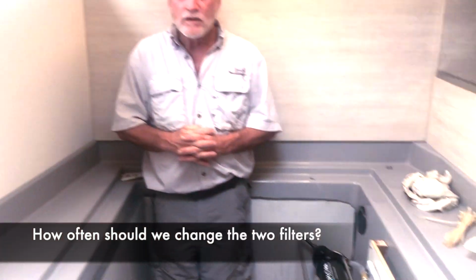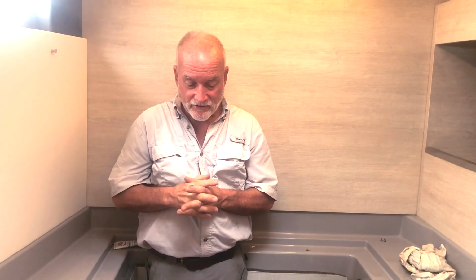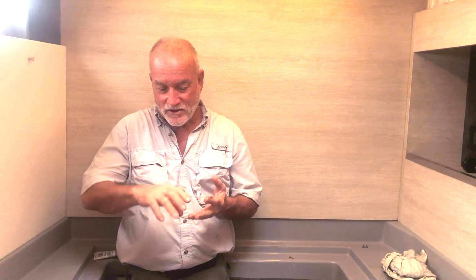This is like an early warning detection system for you for what's going on with the membrane. How often do we change those filters? That's a good question. This system will tell you when to change them. All right. But if you're using it like you will be, because you'll be living aboard, or you're using it every other day, every third day, you'll probably on average change them every 30 to 45 days in nice clear water. The other thing, like I said, there's a lot of workarounds in here. If sensors fail, salinity probe fails, flow testers fail, we can get in the program and take those offline, and the Watermaker keeps working. Okay, so you're not out of water.